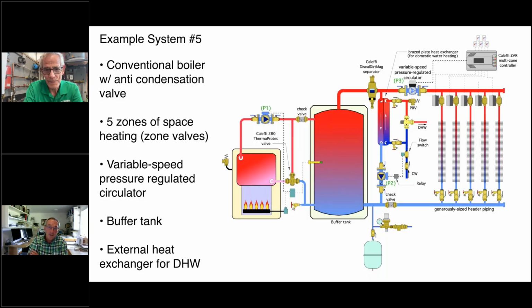Yeah, and quite honestly, this is very similar to what combi boilers use today. They route hot water, space heating water I'll call it, through a brazed plate heat exchanger using a flow switch to basically set up a valve that creates that flow. So it's a detail I wanted to show just to get you thinking: when you have a standard buffer tank and somebody says, I need domestic hot water, you don't always have to use an indirect water heater to do that.